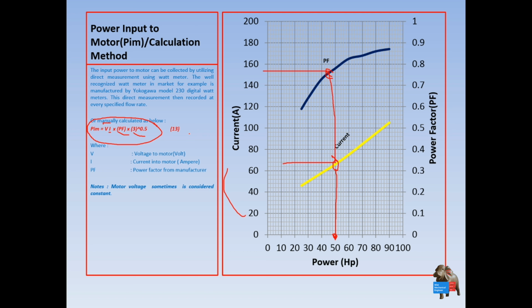But the power factor of the motor actually depends on the current, or the load of the motor. As you can see in this graph, the power factor is not linear compared to the current. An AC motor itself has a graphical performance. So why do we need this? We need to understand that there is no linear correlation between ampere, power and the power factor, because if it is not linear, you have to ensure the correct power, how much power is actually drawn by the pump, or transferred to the motor and to the pump itself.